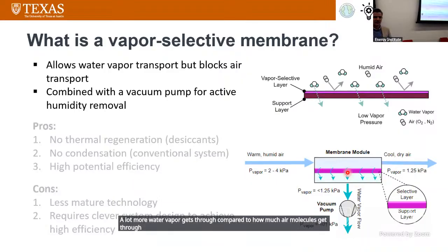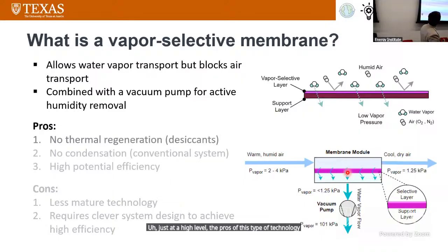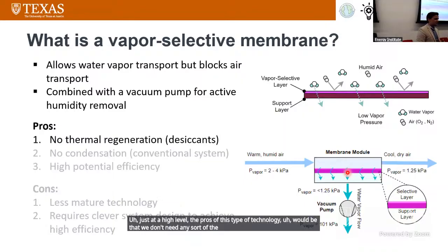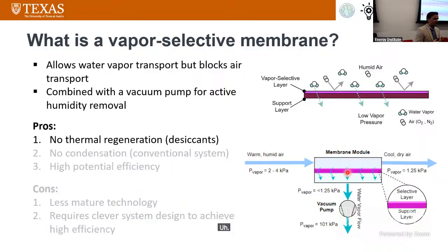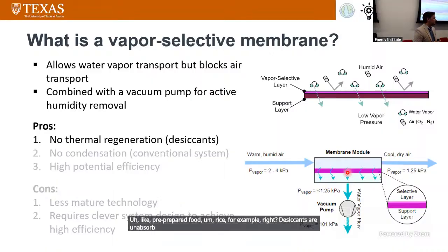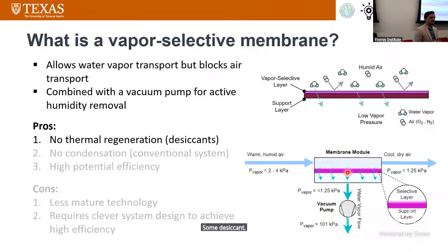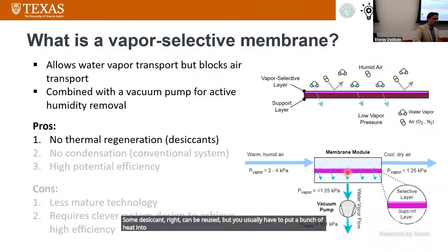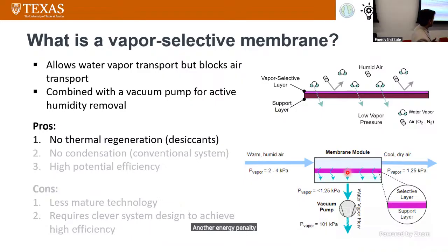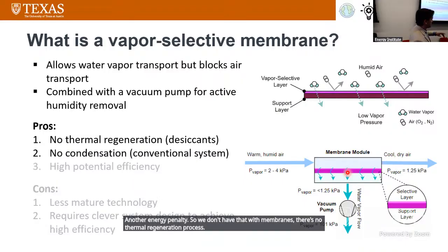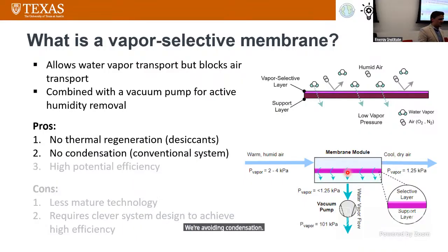We'll talk about why that is, but at a high level, the pros of this technology are that we don't need thermal regeneration. You may have seen desiccant packets in pre-prepared food like rice—desiccants are absorbents, and some can be reused, but you usually have to put a lot of heat into them to force the water back out, which is another energy penalty. With membranes there's no thermal regeneration process, and we're avoiding condensation, which is a big energy penalty in conventional dehumidification.